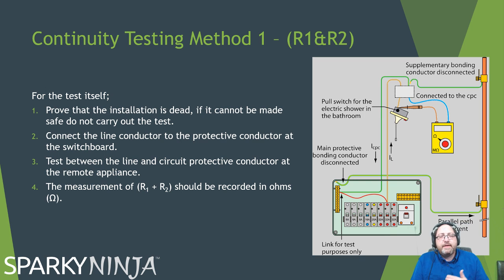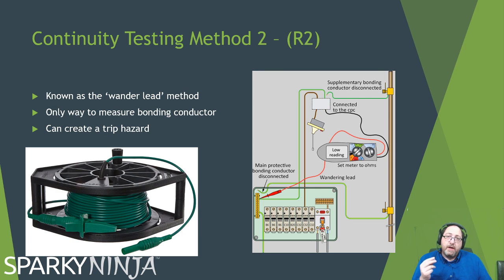We're using the line as a return path to make testing simple. We link it at one end, we test it at this end. Good job. But the point of the test is to verify the earth is continuous. So alternatively to method 1, we could also use method 2. Method 2 is just testing R2. So we haven't got a return line, so what we use instead is a wander lead.